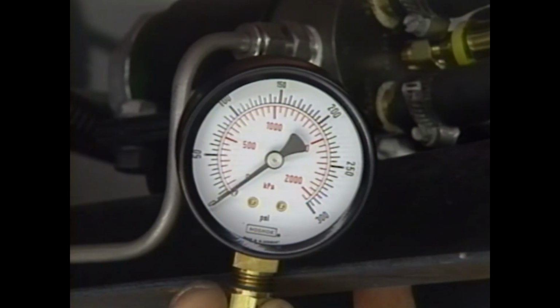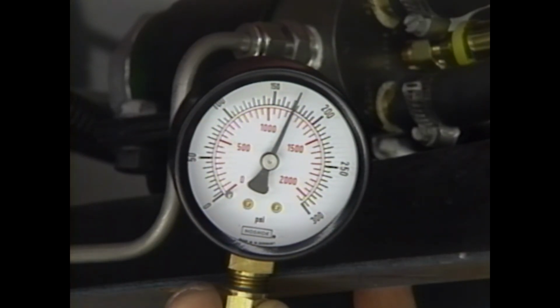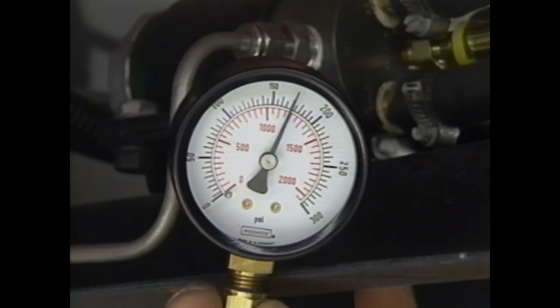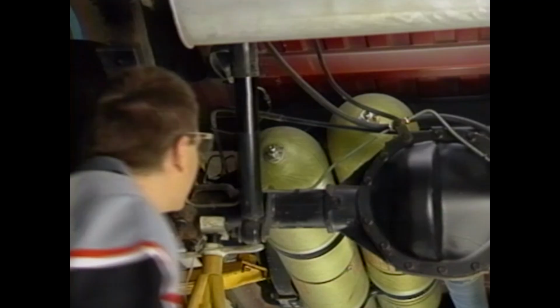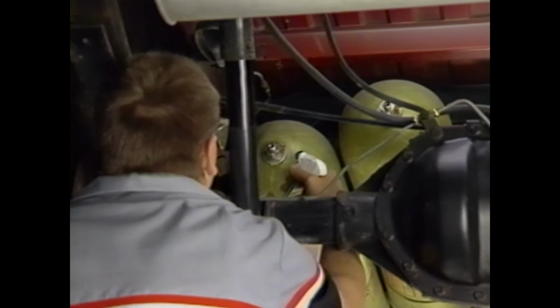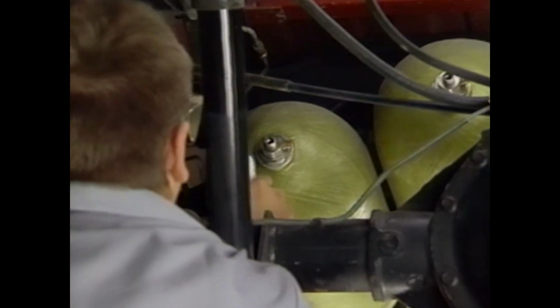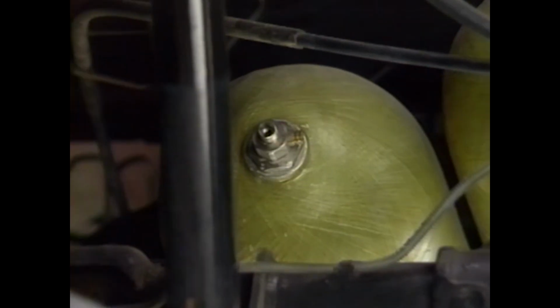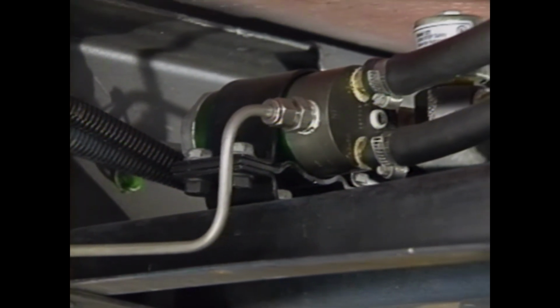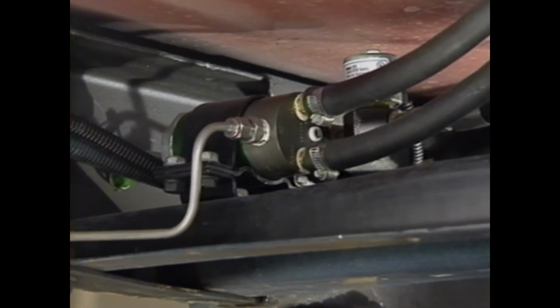When the fuel system is charged up, the pressure should hold at about 175 pounds for about 1 minute. If it doesn't, look for leaks using soapy water at all the connections or any other suspected area. Bubbles will appear if a leak is present, and there's always that distinctive natural gas odor to let you know there's a leak. If the pressure regulator is leaking, replace it. Don't try to repair it.